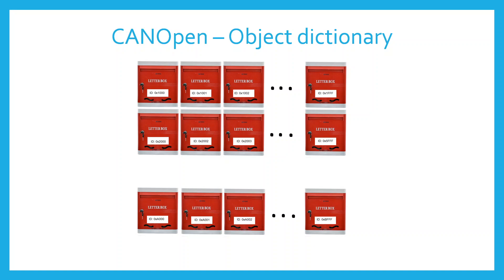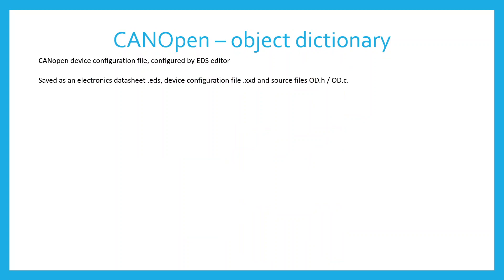The object dictionary is a configuration file specific for each device. It is configured by an EDS editor. It contains a list of variables, its indices and subindices, data types, length of data, and attributes. Each object has its dedicated index. Some objects such as arrays or records have also subindices.